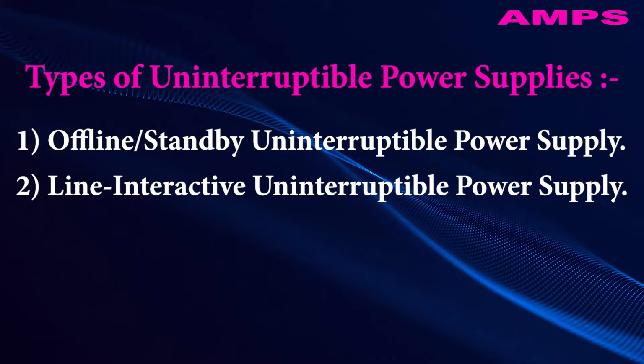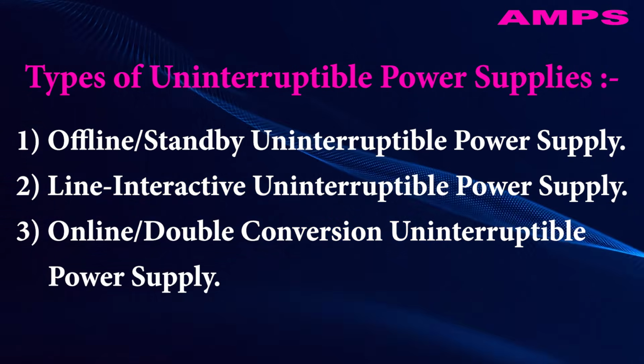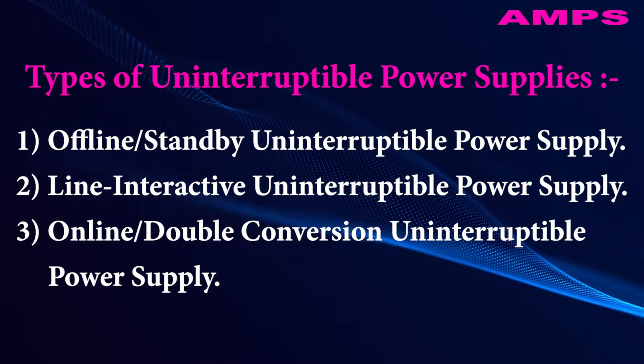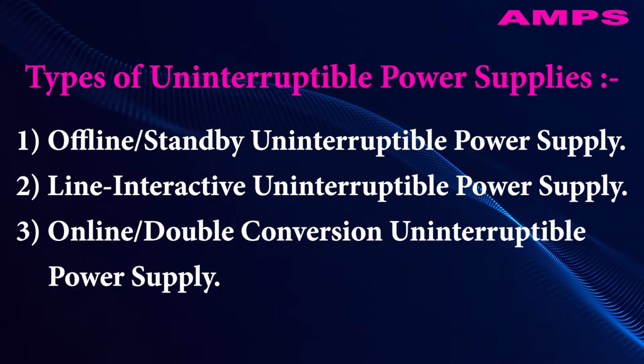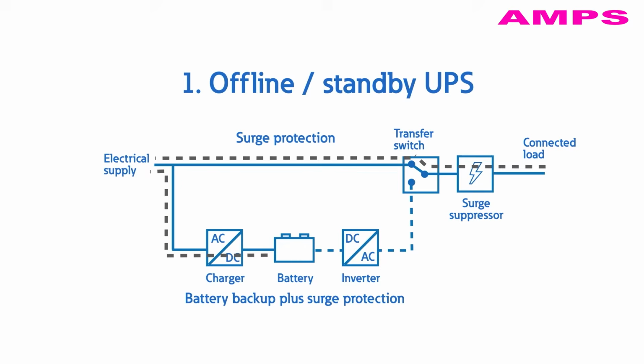Types of uninterruptible power supplies. 1. Offline or standby uninterruptible power supply. 2. Line interactive uninterruptible power supply. 3. Online or double conversion uninterruptible power supply. The offline or standby UPS is the most basic out of the three.